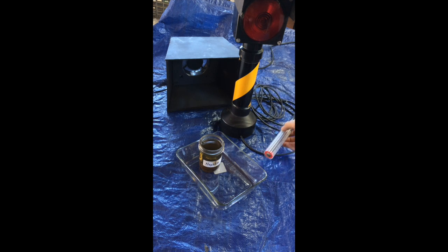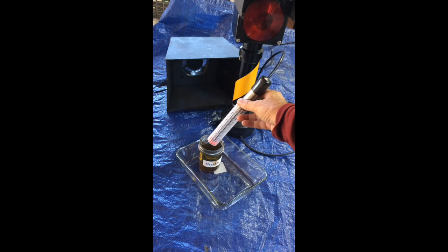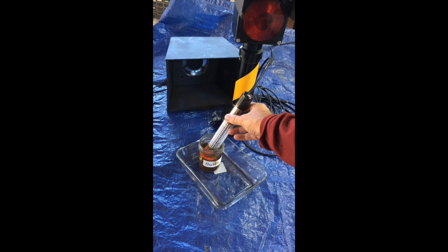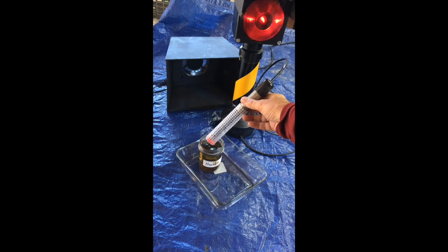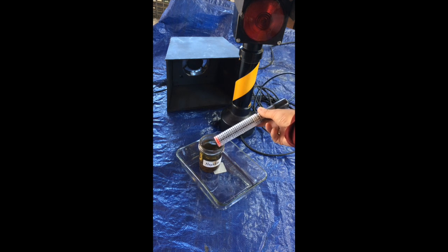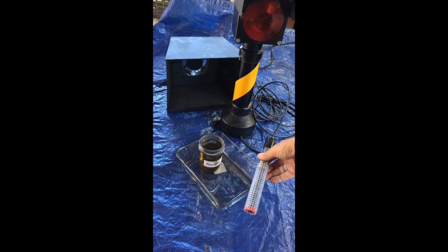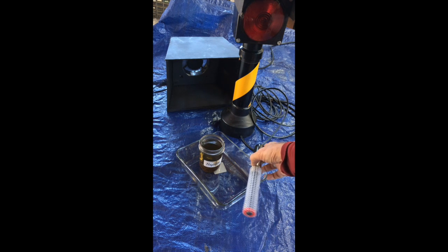So now we'll put it into the naphtha, and this should take a little bit longer to respond, but as you can see, it's still pretty quick. And the reason it takes a little longer is a completely different detection mechanism for the hydrocarbon fluids. Now I'll let this begin to evaporate. This takes quite a bit longer than does the brine in terms of reset, but it still should reset in about 15 to 20 minutes.